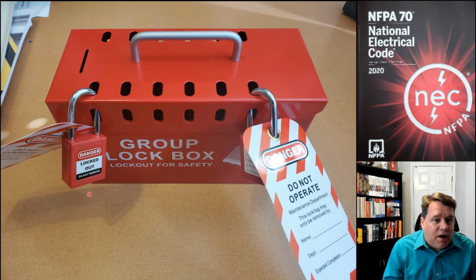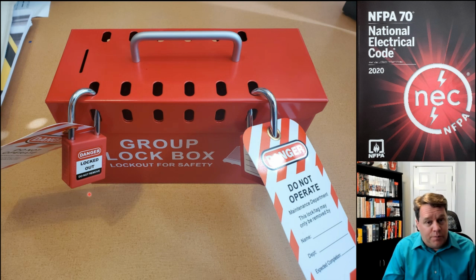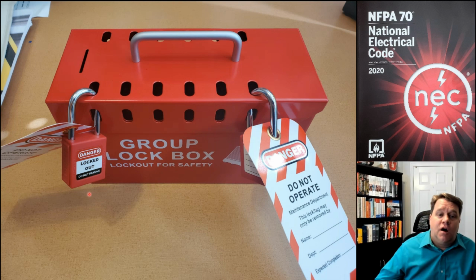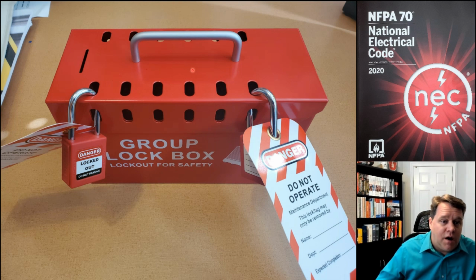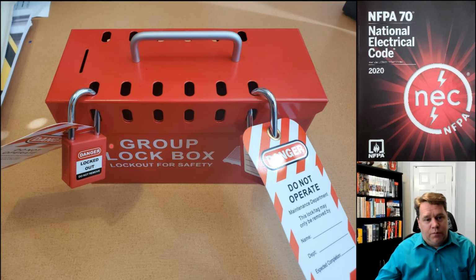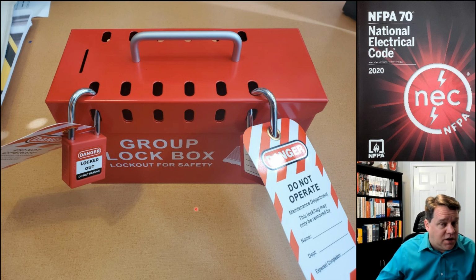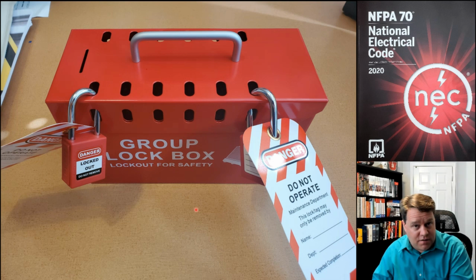Lockout tagout program might be simple or it might be complex. If we have multiple people that are going to be working on a piece of equipment, we might have to have something like a group lock box where we have one master lock and we drop the key inside of this box, and then everybody puts their own lock onto this, and that way I can't open the box and get the key until everybody is complete.